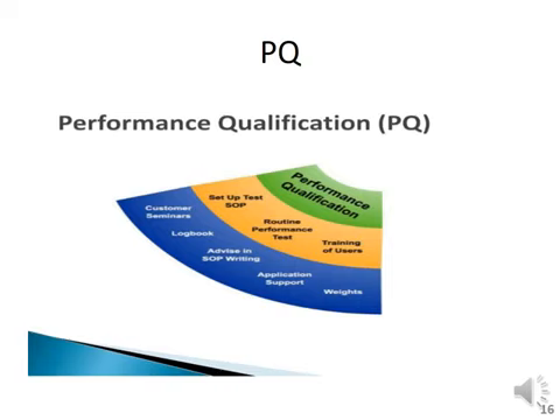In the third circle you can see other important factors regarding the performance qualification: the customer seminars, in which you are guiding the customers; the logbook, in which you are keeping the data and information according to the manufacturer's guidelines about the performance; advice in the SOP writing, because whatever you write in a standard operating procedure, there is always a proper guideline about those writings. Application support, application of the system, application of the instrument, whatever support is required, that detail is given, and the weights you are using. These are secondary requirements for the performance of the machine, and weights are one of them, right?